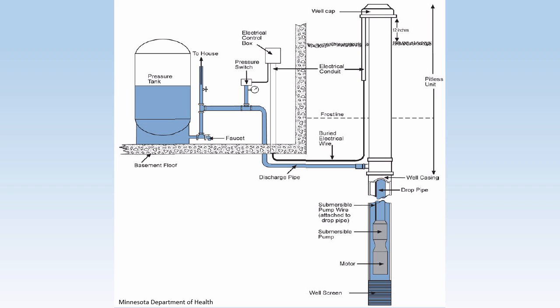When there is heavy water use, the pressure tank may not have enough volume to supply the needed water, and will eventually need help from the pump to keep up. When the water use stops, the pump will continue to run, filling the tank and increasing the pressure in the system until the cut-off pressure is reached. The larger the tank, the more water that can be stored with sufficient pressure. If this is your situation, increasing the size of your tank or adding a second tank will provide more water at a higher pressure, before relying on the pump to help keep up.